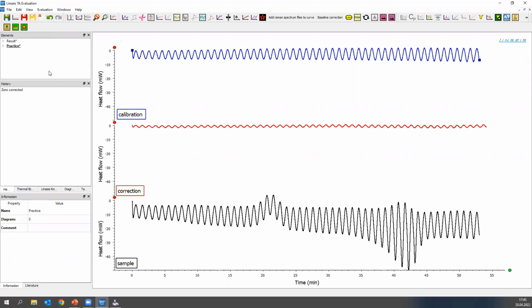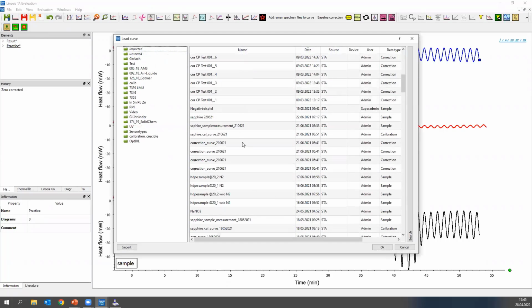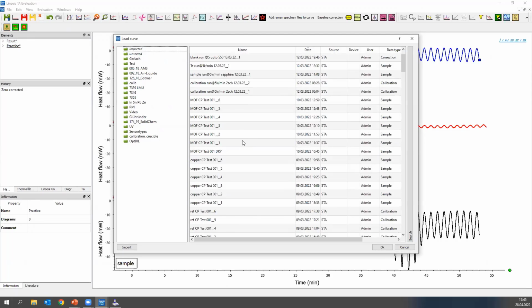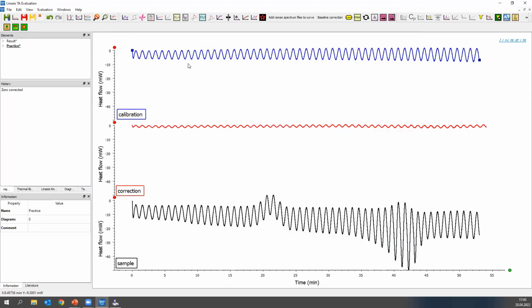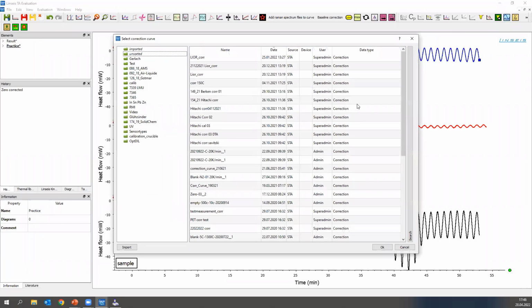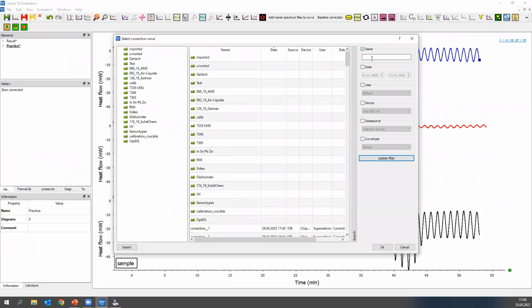This is our evaluation software. You can load all your measurements, and it depends on you how to organize them here. There's the modulation button. The modulated evaluation separates the reversible and non-reversible parts of a modulated DSC curve and calculates CP. Now I want to create a calibration, and I have to check for the right curve here. I think I've called it something like modulated.